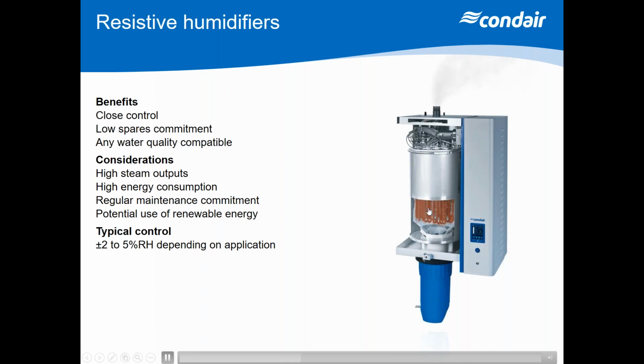Now, you can see on the diagram here that we no longer have a plastic cylinder because we're using resistive heating elements. So the water isn't live. We're not passing current through the water. So how this unit works is that when we get a demand signal, water will fill in this cylinder and the water level will be controlled between a series of float switches. So we will always control the amount of water. But to get modulation out of it, we'll pulse electricity to these heating elements at a rate relative to the control signal. So if I've got a 0 to 10 volt control signal going to this unit at, let's say, 5 volts, it'll pulse on and off every other cycle in a 10 cycle period.